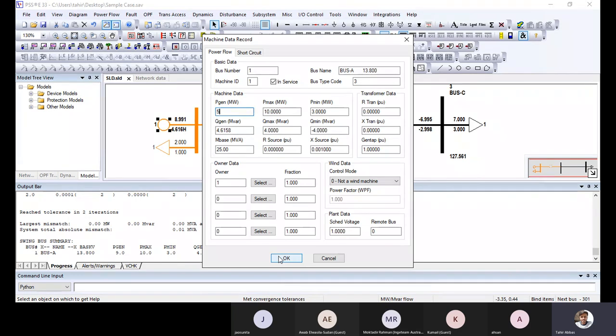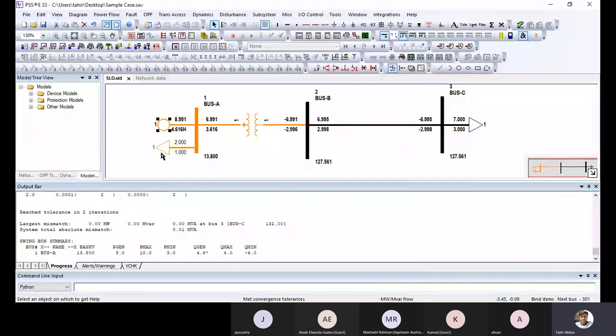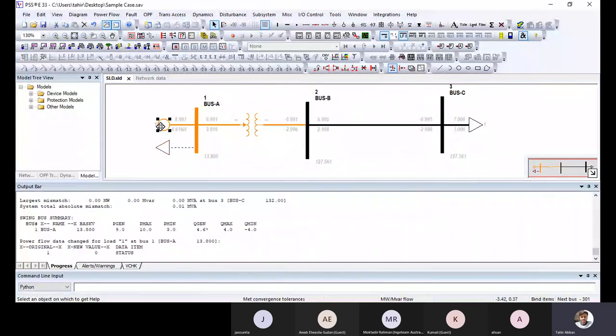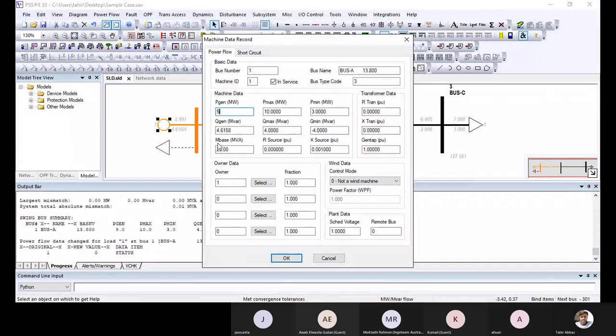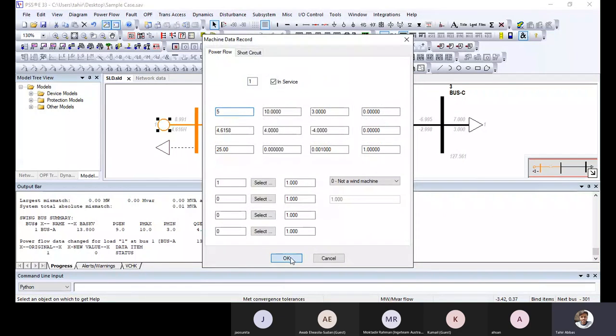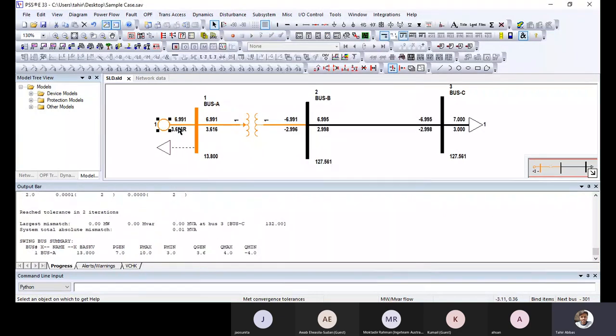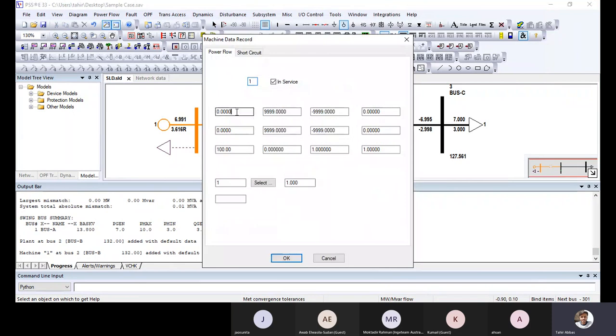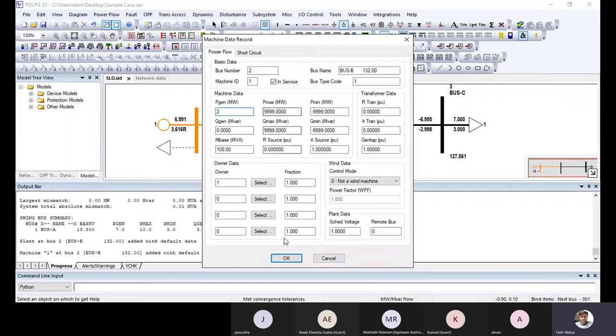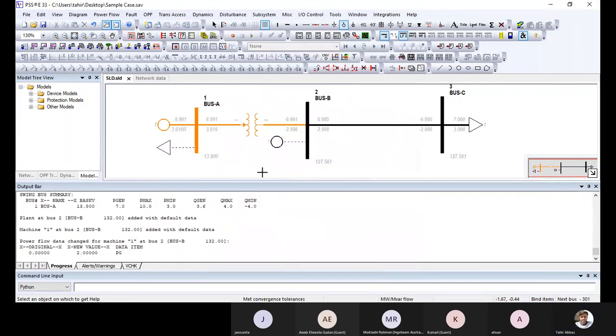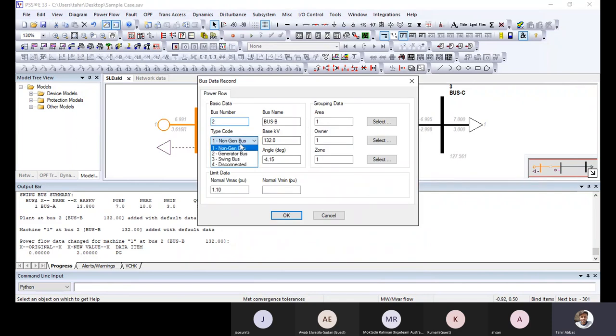Let's see. First, I'm switching that generator so that the case will be real. Now I'm adding 5 megawatt. Okay. Now I'm solving the case. Now you can see again, swing goes back to 7 megawatt because demand is 7. Okay. Now what I do, I add a generator here, like it is 2 megawatt. Forget about the Pmax, Pmin. Why is it disconnected? Because this bus is non-generator. Make it a generator bus, now it will be fine.